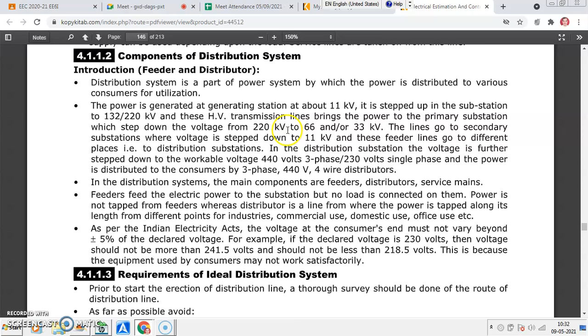So the distributor is especially associated with voltage drop. Voltage drop is the major criterion: the voltage drop at the far end of the consumer should not be more than ±5% or 6% of the rated voltage. Accordingly, you design the distributor. So the major difference between the feeder and distributor is that the feeder has no tapping, the distributor has tapping. Normally consumers are connected to the distributors. So you should take this major thing into account, whether it is a feeder or a distributor. The system may be either underground or overhead.